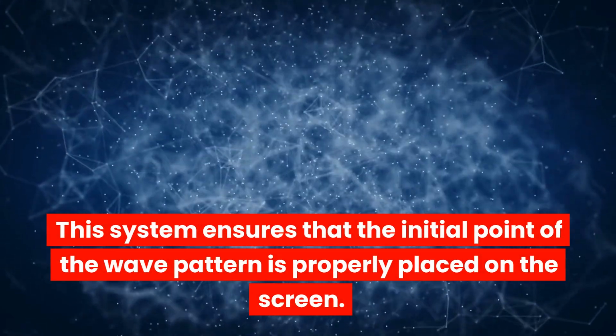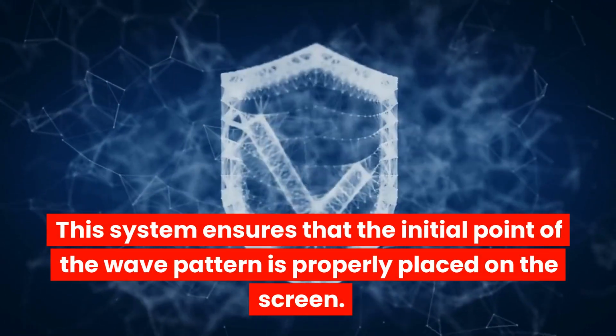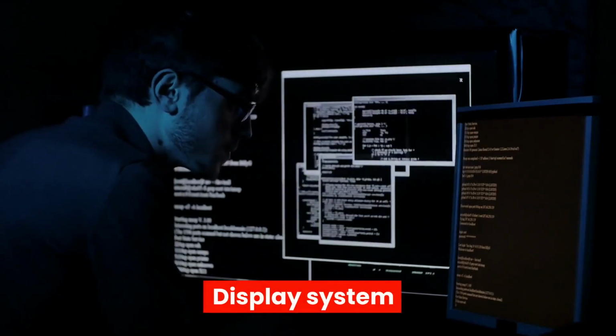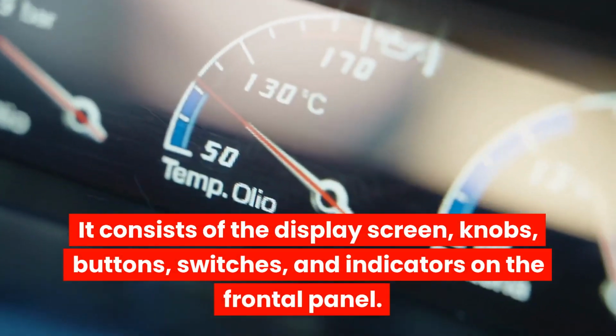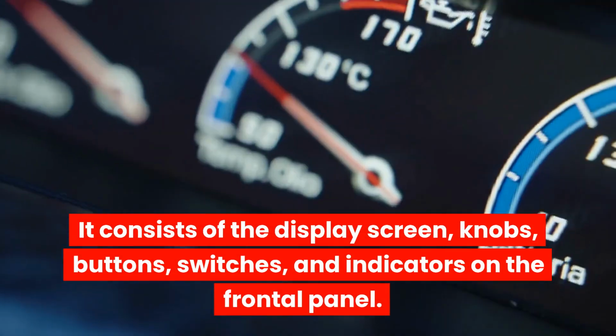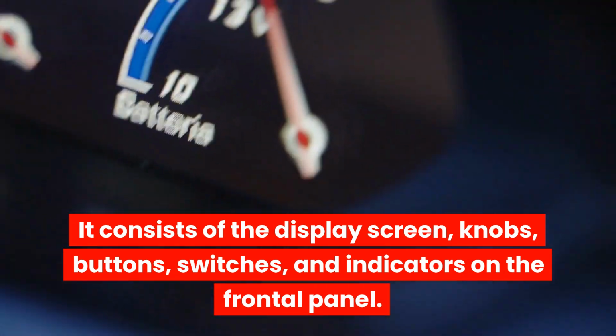Trigger system. This system ensures that the initial point of the wave pattern is properly placed on the screen. Display system. It consists of the display screen, knobs, buttons, switches, and indicators on the frontal panel.